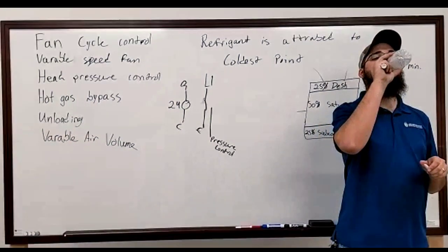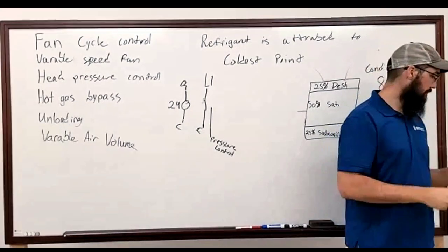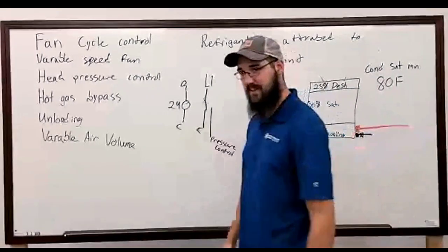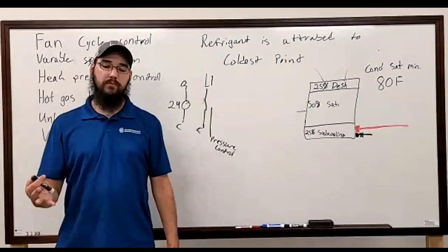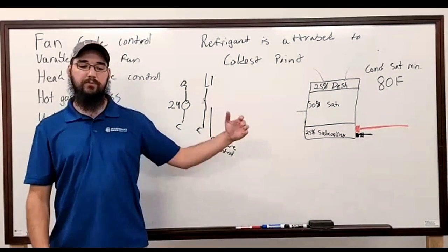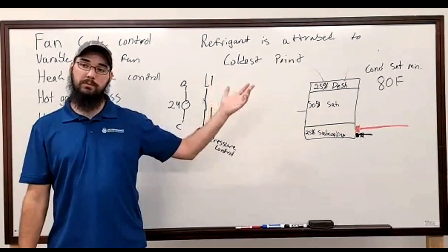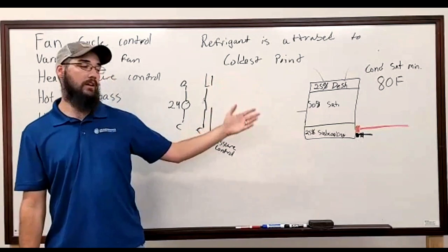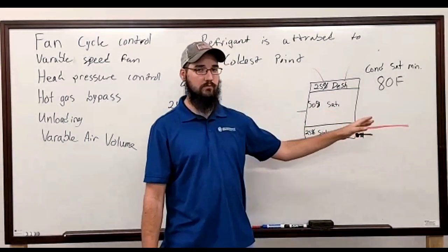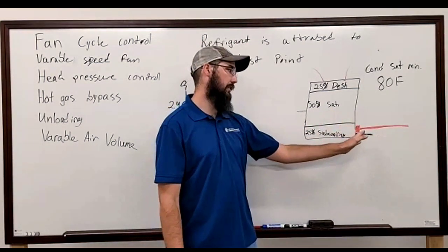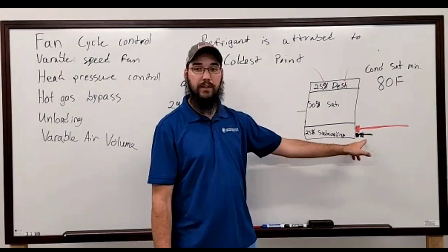Where the, just inside the condensing unit. As soon as you get inside the condensing unit, it's a TXV right there. You see a lot of stuff. So this one you're talking about, it'll be on the outside, before it hits the unit? Yeah. So Casey's question was, most systems we open up, especially on RTUs and unit split systems, we see a TXV on the inside, not on the outside of the system. In this particular case, this will be on the outside, and it won't be a TXV, it'll be a piston.